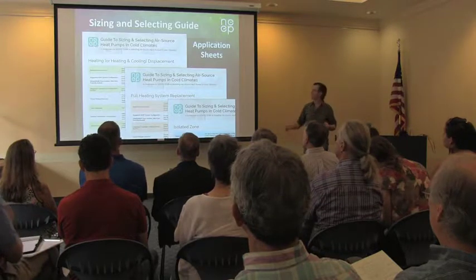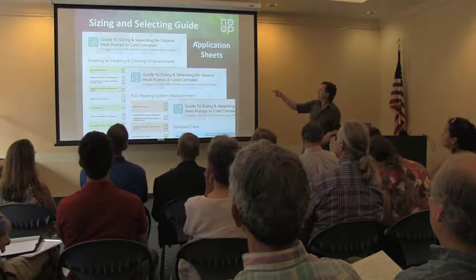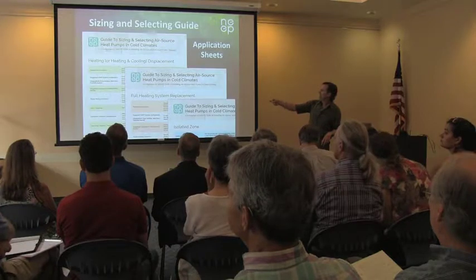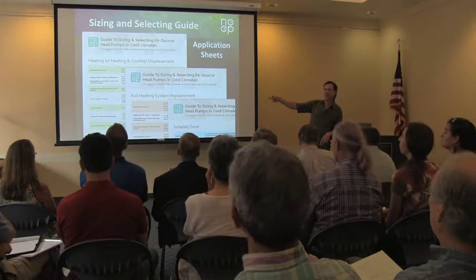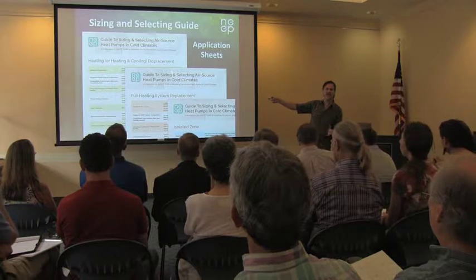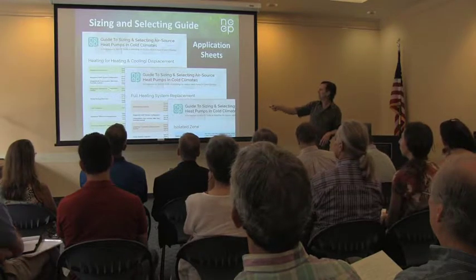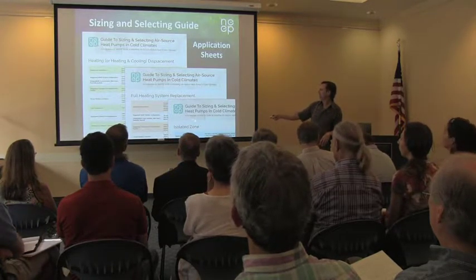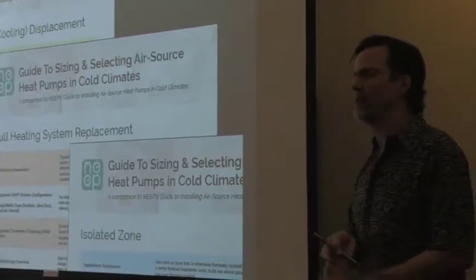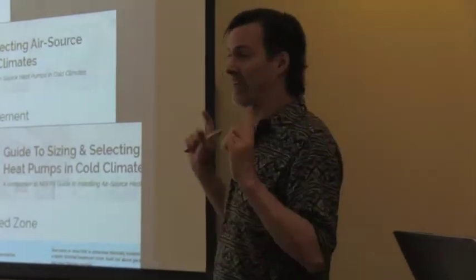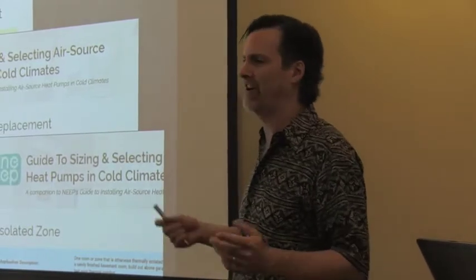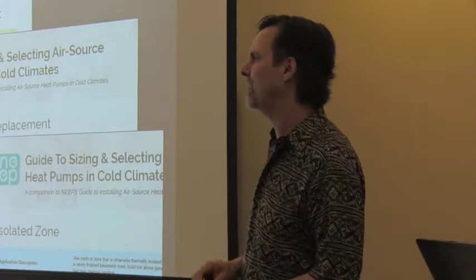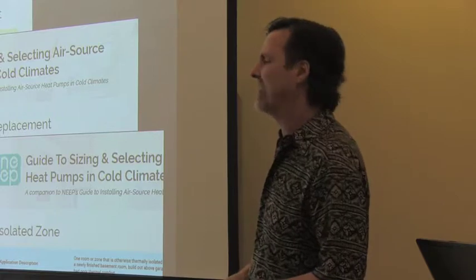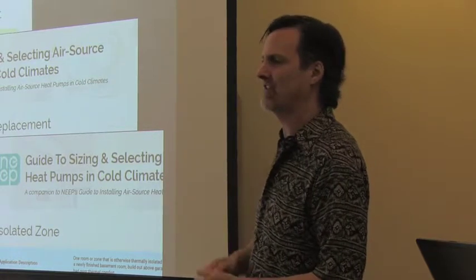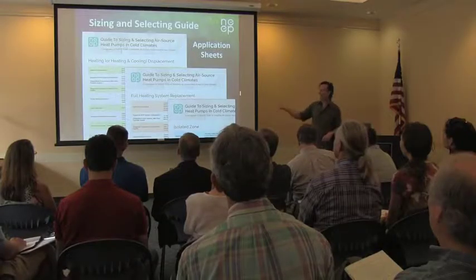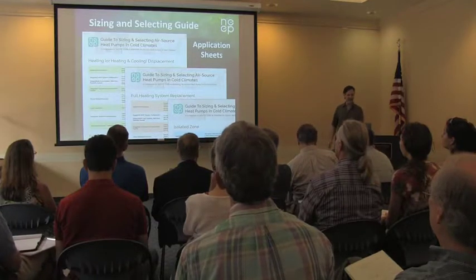This is just a view of what the sizing and selecting guides look like. Basically, there are 5 separate sheets, depending on whether you're putting it in an existing home to displace an existing heating system, doing a full replacement, or doing an isolated zone. There's another one for new construction, and there's actually one for cooling focus, because some customers, frankly, really just want cooling and don't care about their heating. I think they should still take advantage of the high efficiency of a heat pump because it doesn't cost that much more to install. But this is just kind of a map of what that looks like.